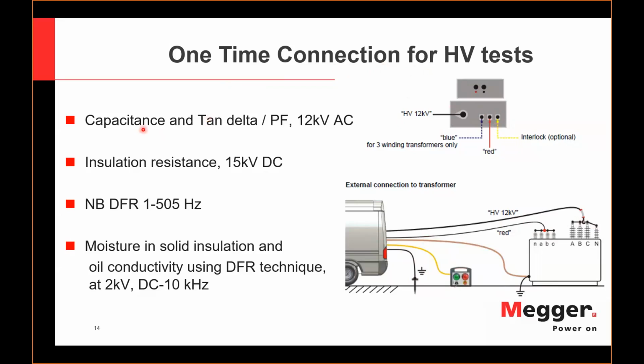What kind of tests can you do with this one-time connection? Capacitance and tan delta, and output AC signals or AC voltages up to 12 kilovolt. You can conduct insulation resistance with guard up to 15 kilovolt DC. You've seen this abbreviation before. It's a narrowband DFR, very valuable 1 Hertz values that are done to assess the condition of bushings or windings.